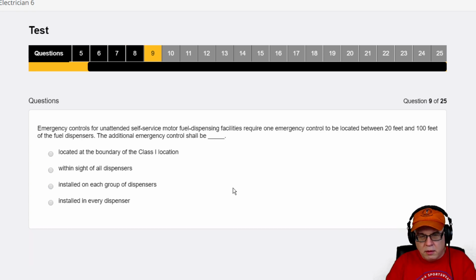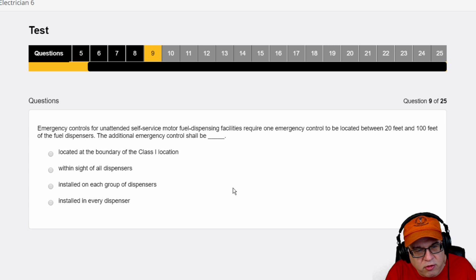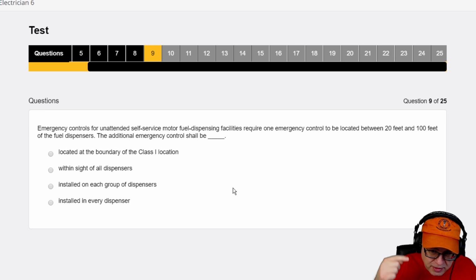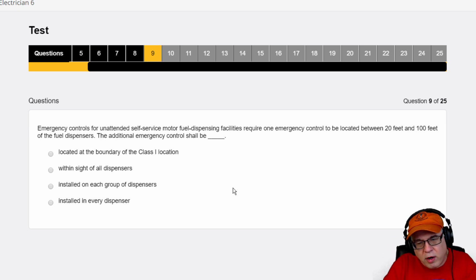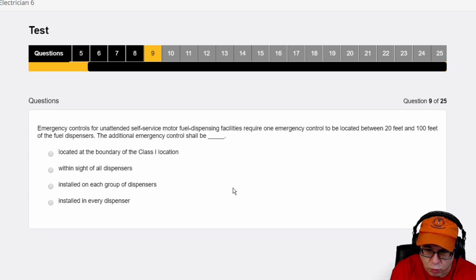This one says emergency controls for unattended self-service motor fuel dispensing facilities. That should tell you guys who are familiar with this right away where it's at. It requires one emergency control to be located between 20 feet and 100 feet of the fuel dispenser. So at least one has to be between 20 and 100 feet. An additional emergency control shall be located at the boundary of the Class 1 location, within sight of the dispensers, installed at each group of dispensers, or installed in every dispenser.